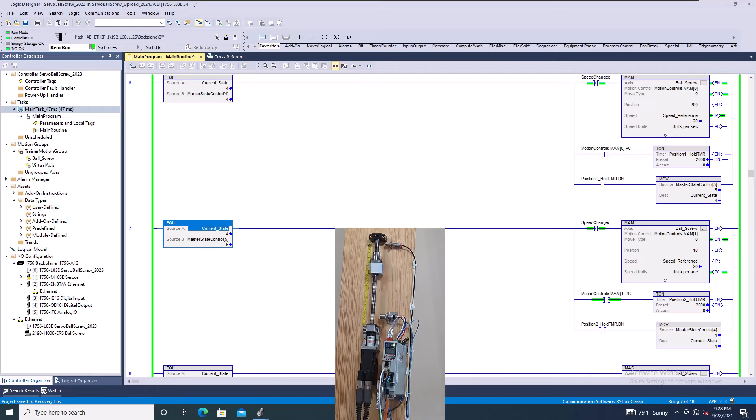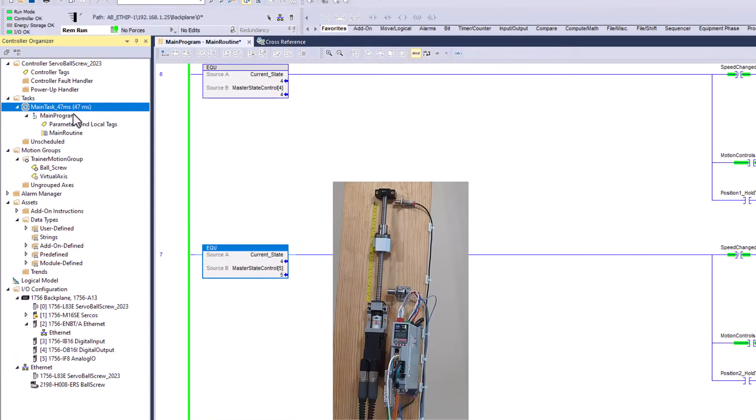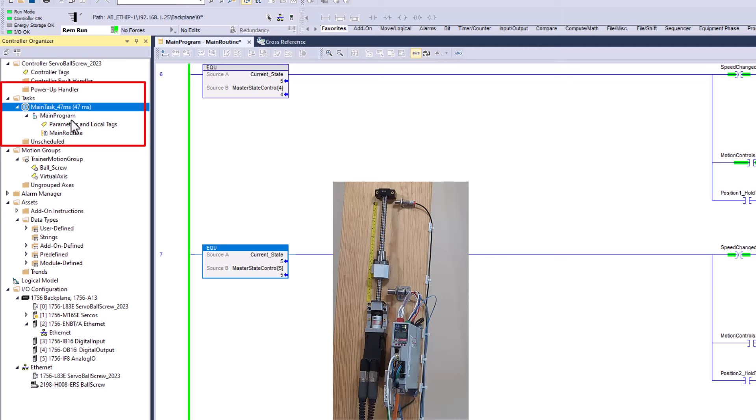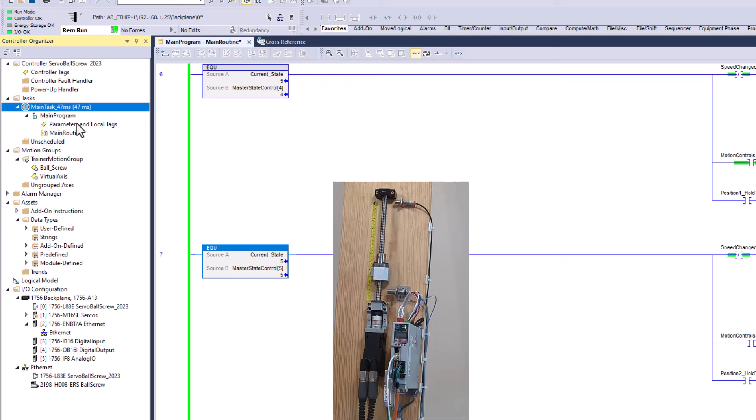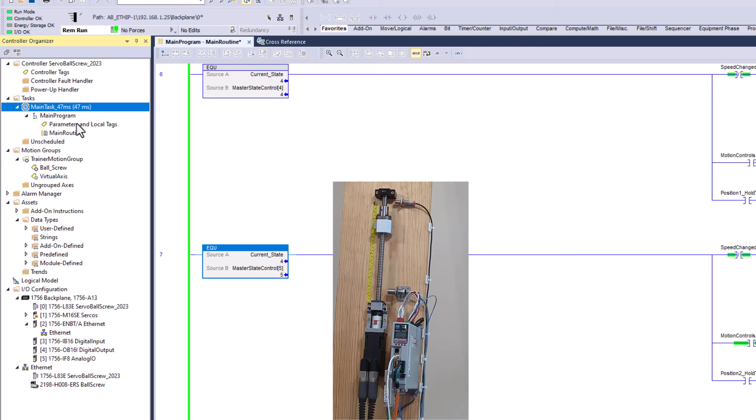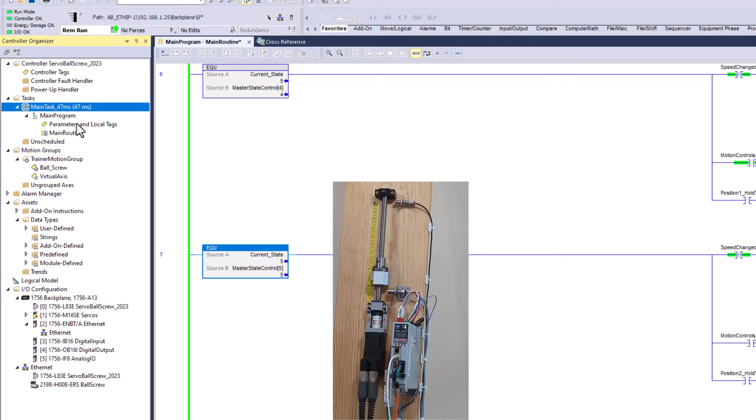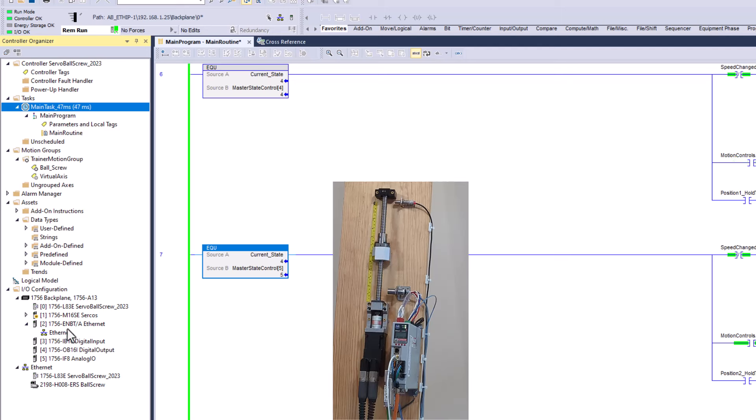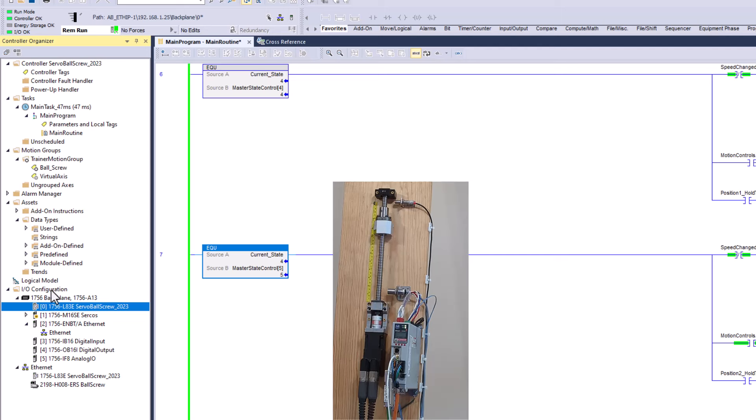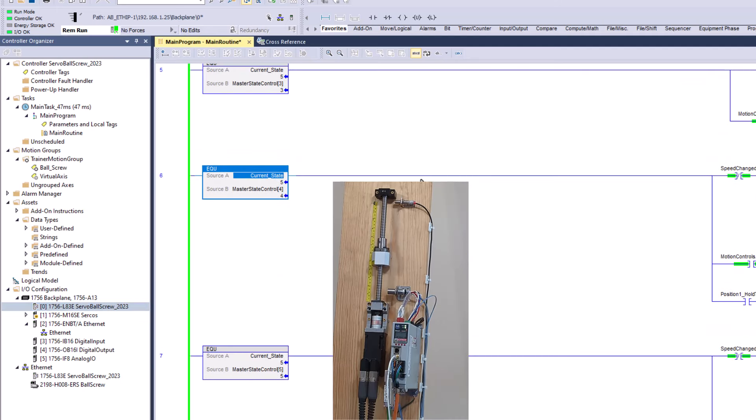If you have your system in continuous task and you're trying to control servos and precision controls, especially CIP Motion, you're really not understanding the timing of the system, the timing of the machine, and the motion of how things should actually work. You always see me use periodic tasks. The reason is because I can define what my machine needs to do when it needs to do it based upon the communication path, how fast my CIP Motion is traveling, how fast my communications is, and how I have my task rate set.